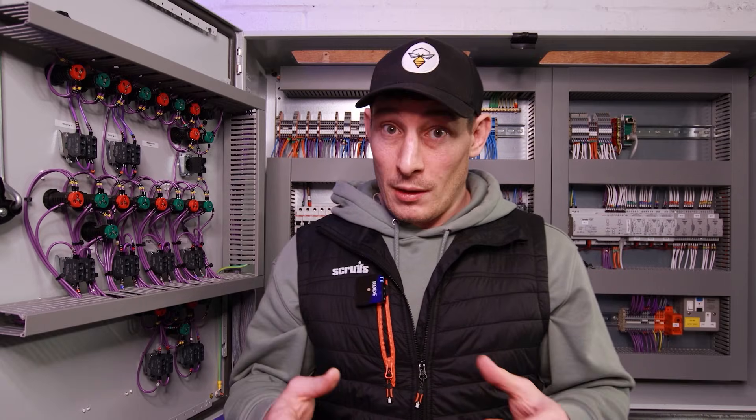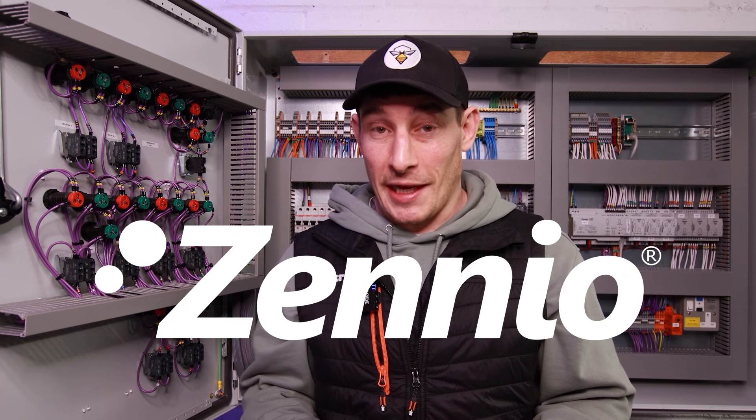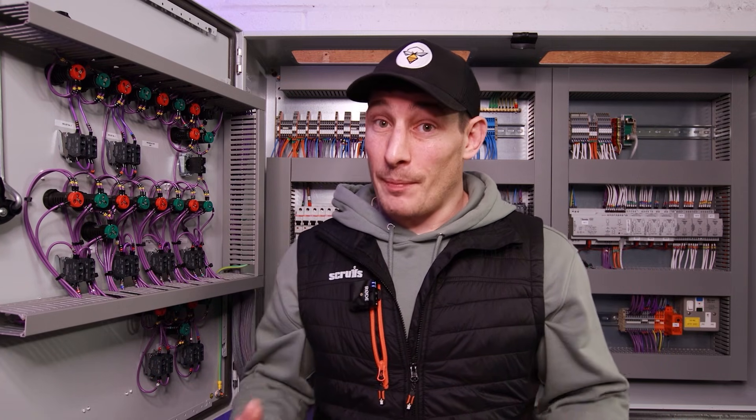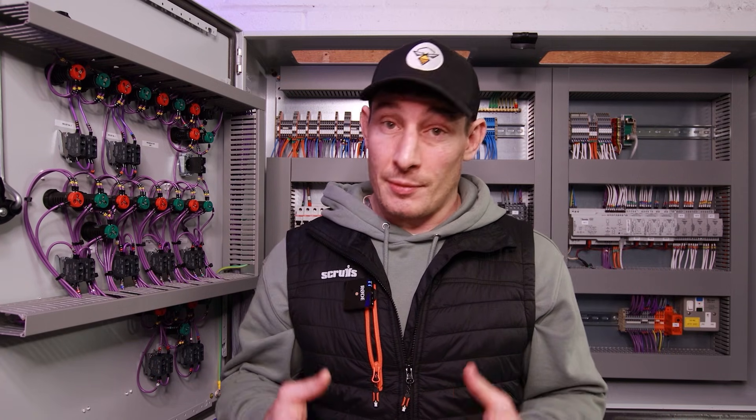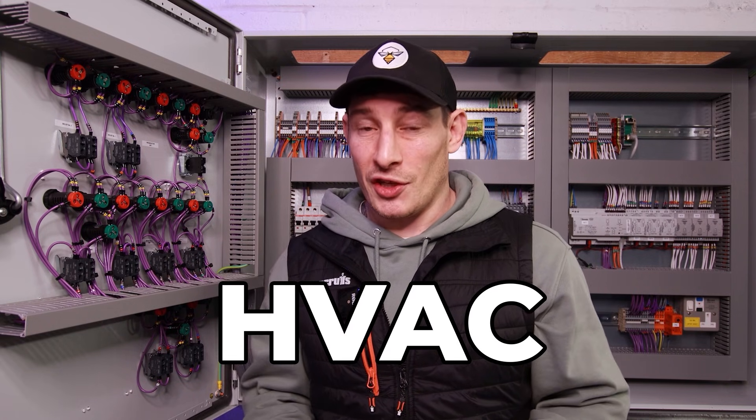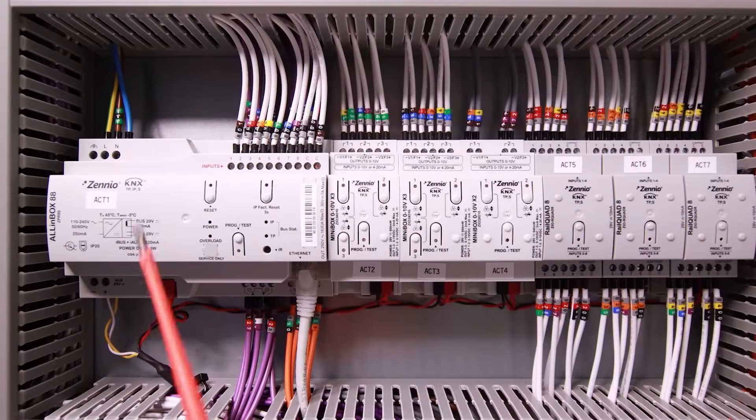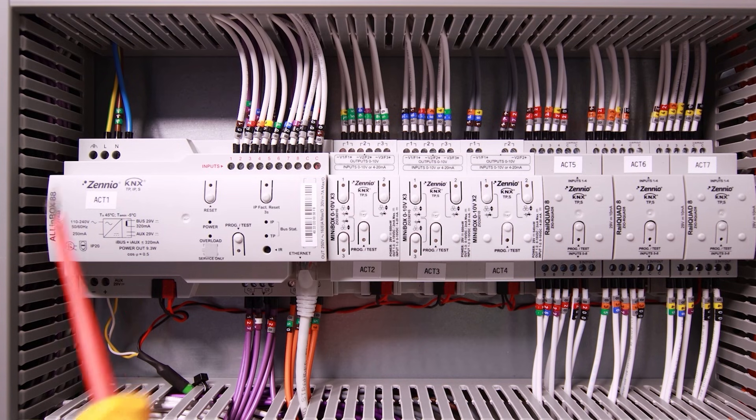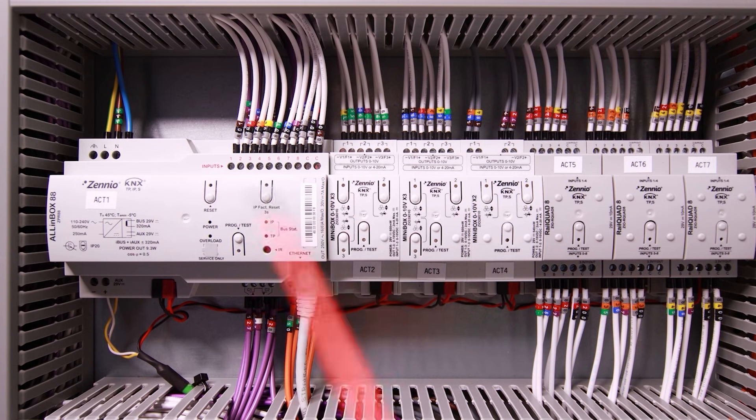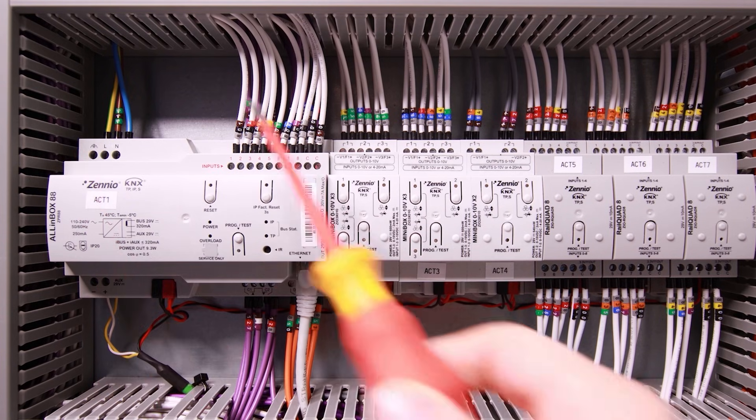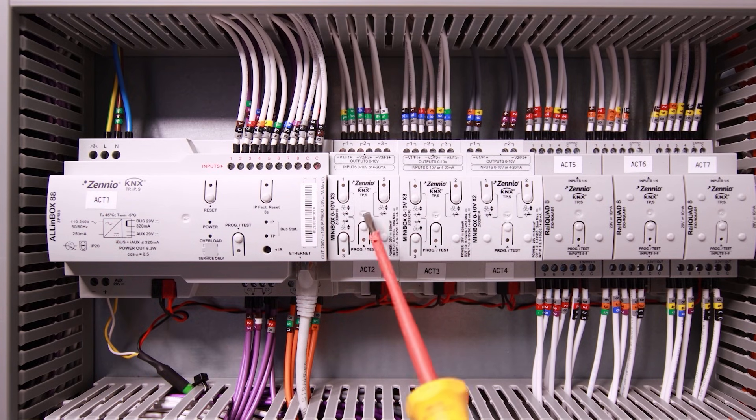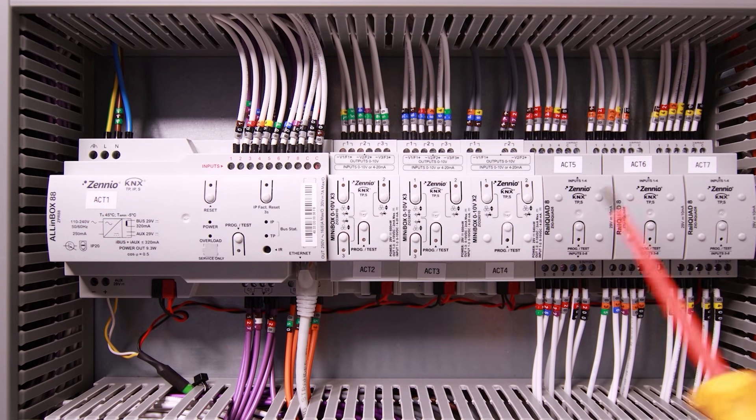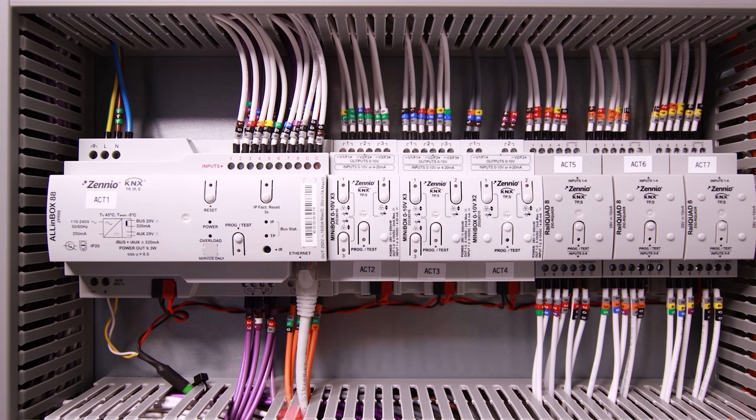Now the PLC we're looking at within this project is a Zennio PLC which uses the KNX protocol. This is a BMS project, a building management system, used primarily to control heating, ventilation, and air conditioning. As you can see here we've got our Zennio modules and like most PLCs they are modular. We've got the main controller here and then various different modules that we tag onto the main controller based on what our I/O requirements are.